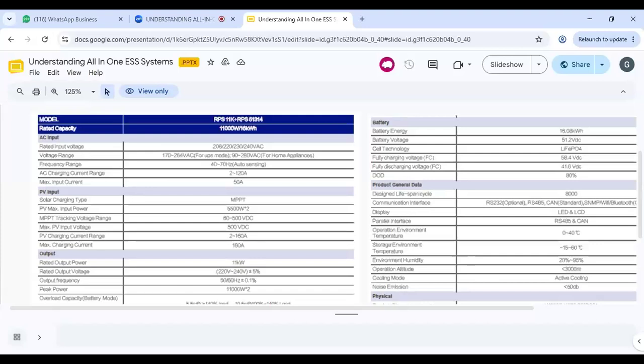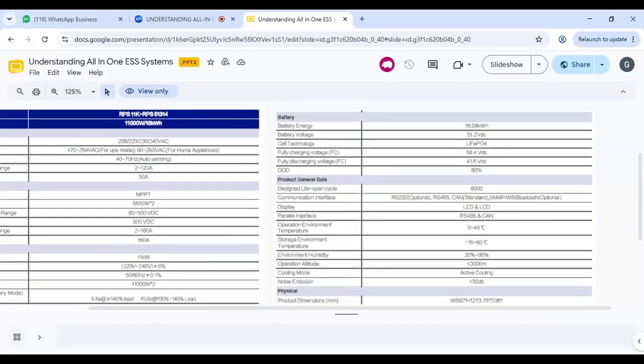Going straight to the battery, 16.08 kilowatt hour is the capacity of the battery. It's a 48 volt system because the battery voltage is 51.2 volts. You can see the low battery cutoff and the battery full voltage. Looking at the design cycle, this is 8,000. The cycle is 8,000. Then you can see the physical size below.